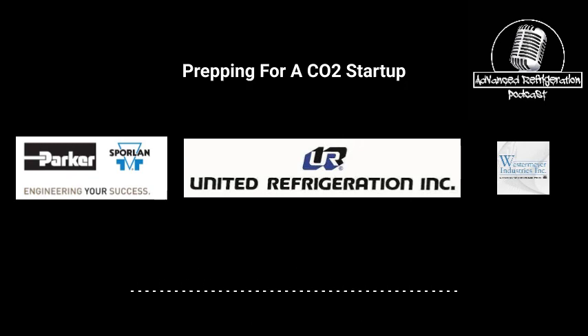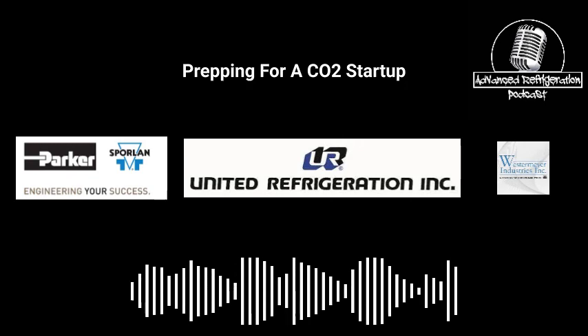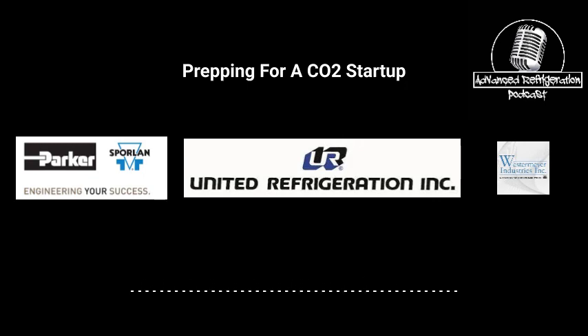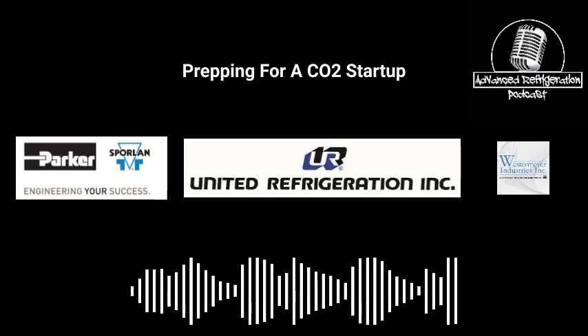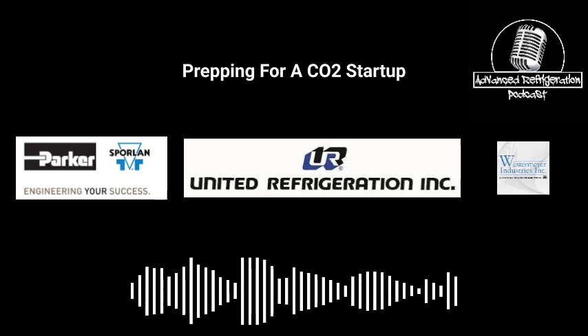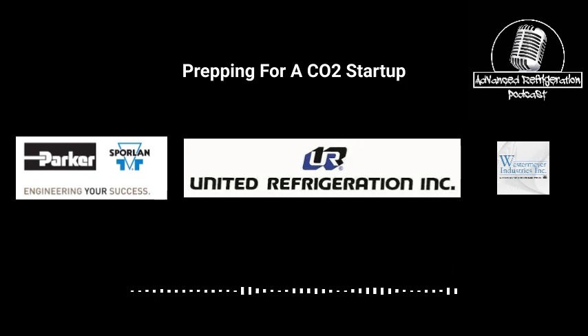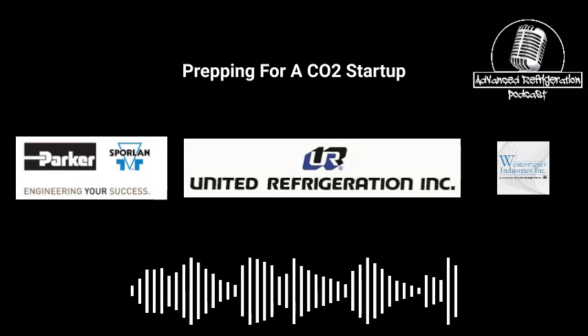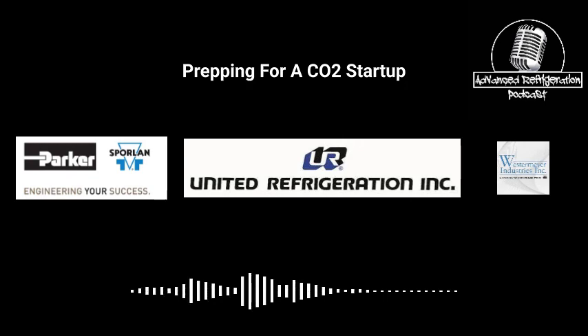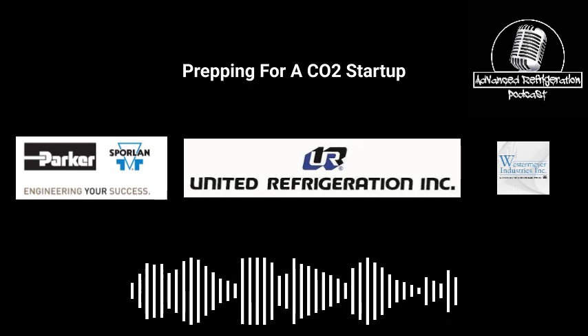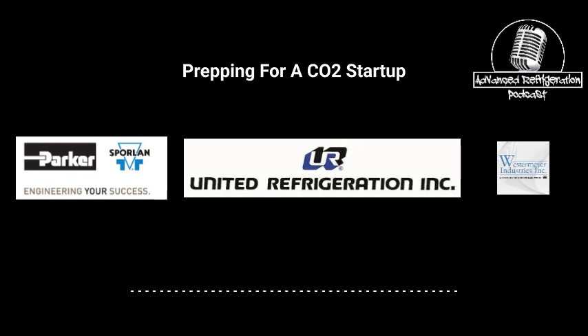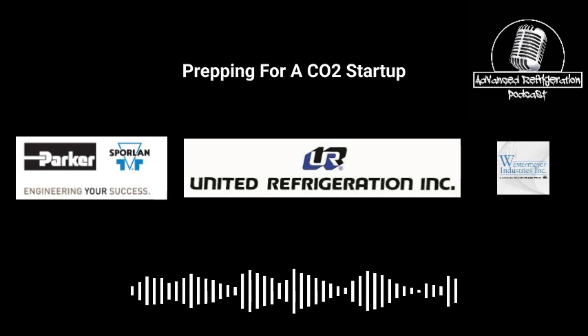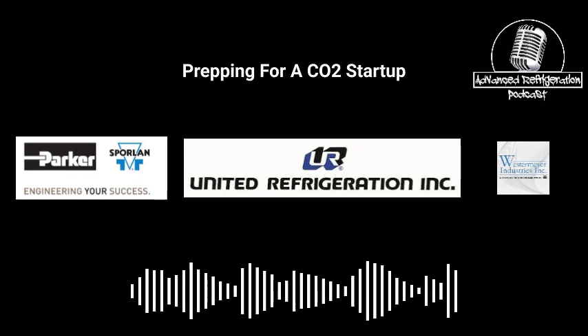So once you get to that part and you've got oil in the rack, now it's go time. Basically, I'll start up medium temp first and start charging it up. You could either charge it to the flash tank, or what I've been doing lately is charging it through the cases, meaning I charge it through and make sure it goes through the liquid dryer.